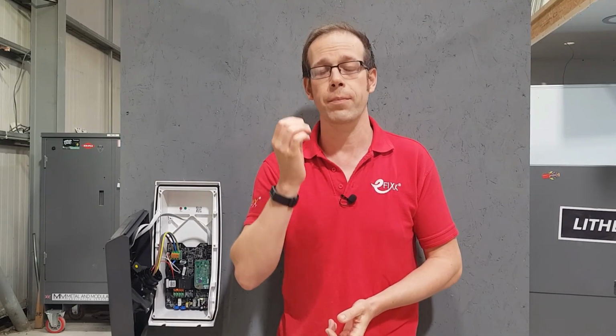If you've installed the charger under circumstances where regulation 722.411.4 does not apply and you're using mode A, or if you're using mode B without the earth reference electrode, then the risk of simultaneous contact must be managed locally, perhaps by inserting a piece of plastic pipe into the pipework supplying the tap to ensure that the bodywork of the car and any local exposed or extraneous conductive parts of the installation cannot be touched simultaneously.